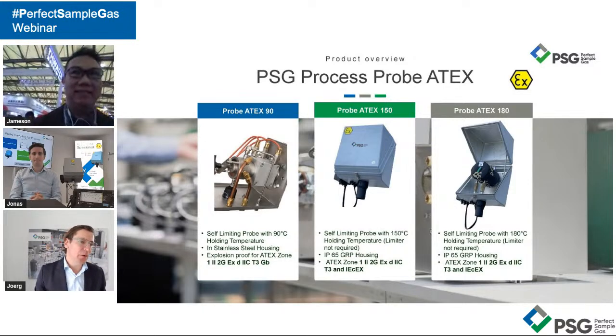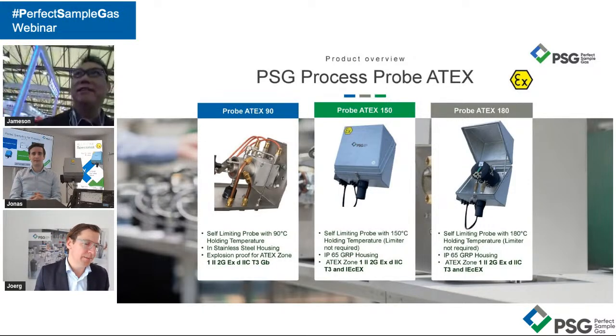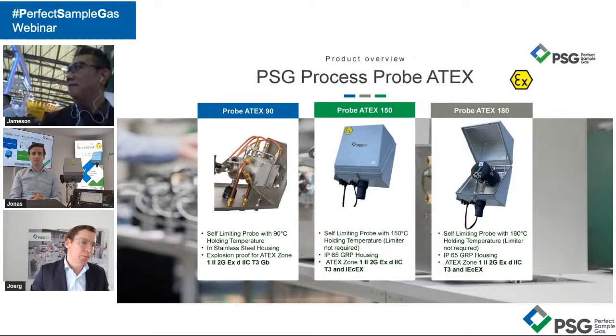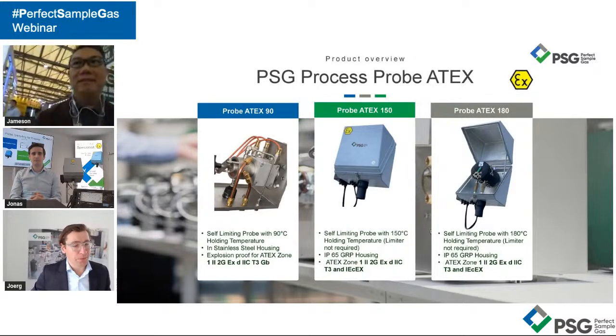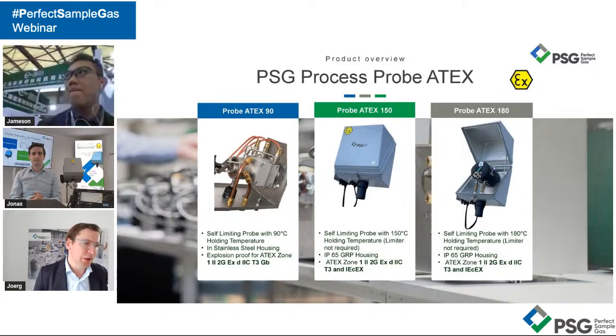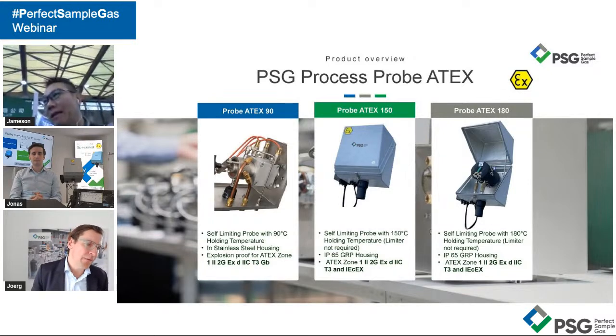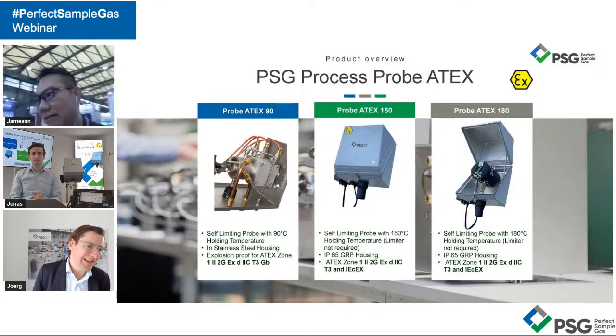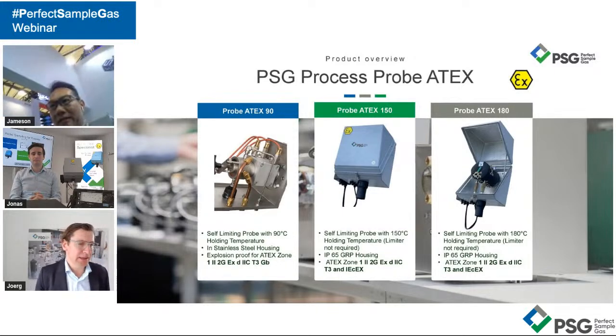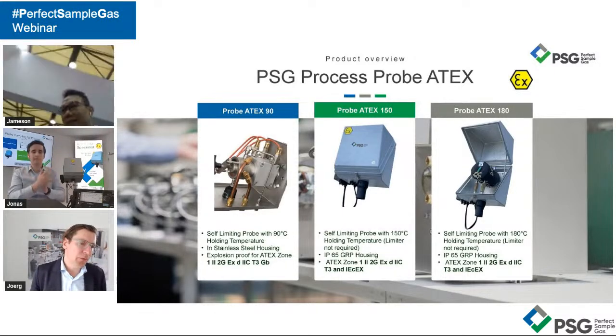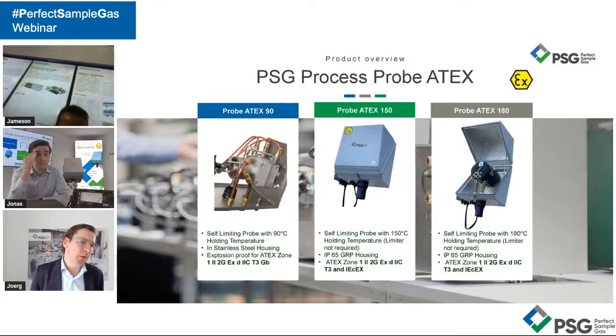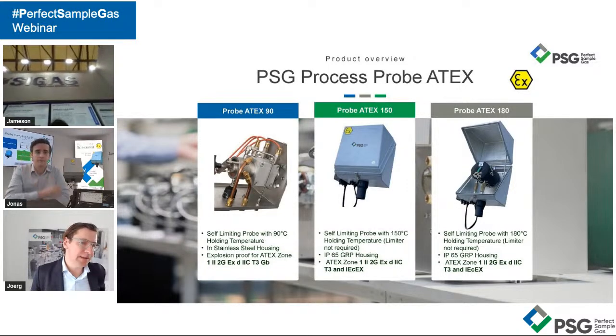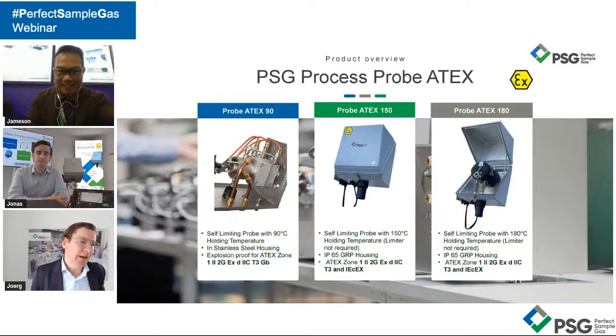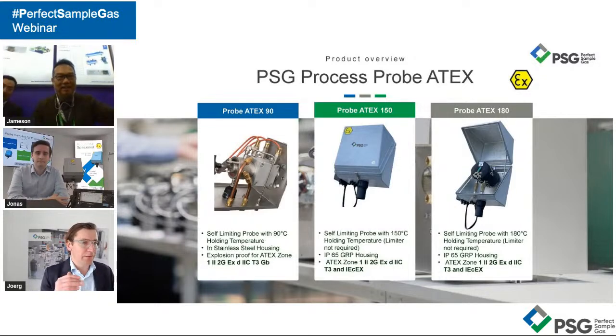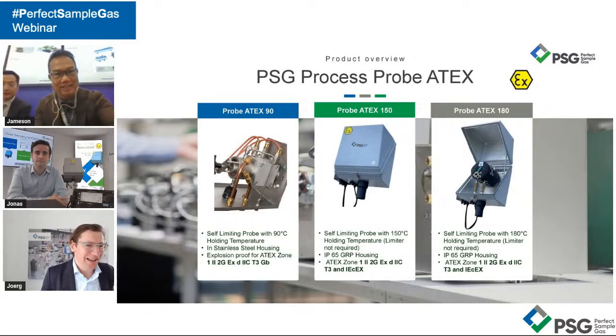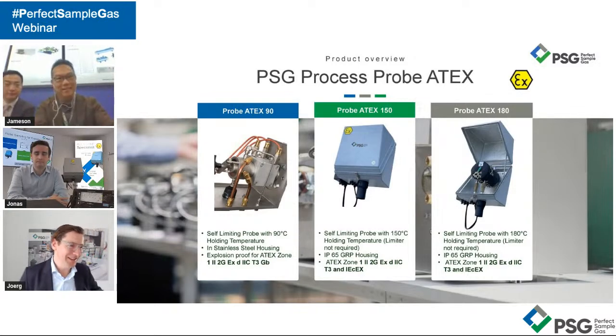And therefore we have a good overview of the PSG process probes for ATEX solutions. So we have one probe for 90 degrees C holding temperature. We have one version of the probe for 150 degrees C, and even this depends on when you have a very high acid dew point, on 180 degrees C.